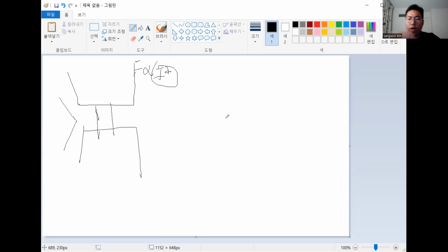Okay, this is the first result. When the current flows and the contact opens, arcs happen. But the matter is, when the arcs happen, welding also starts between the contacts. You know what I mean? As you know, welding is when two metals are attached, making one conductor, right?